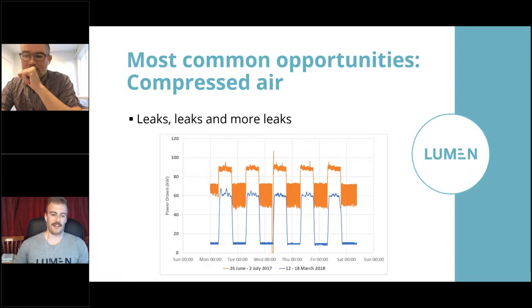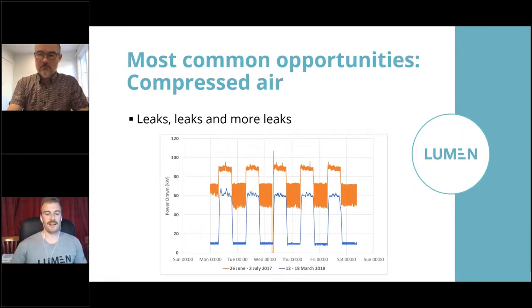And they fixed the leaks, and that's where you see the blue line. So that's afterwards. Once they've fixed the leaks overnight, you can see the load dropped from 60, say, kilowatts down to about 10. So a 50 kilowatt saving in terms of leaks, which is massive. And this was saving them around about 40 grand a year. This also shows the value of energy submetering. If you were just looking at the site in terms of the retail meter, then you'd never see this. It would just be noise in the whole site.